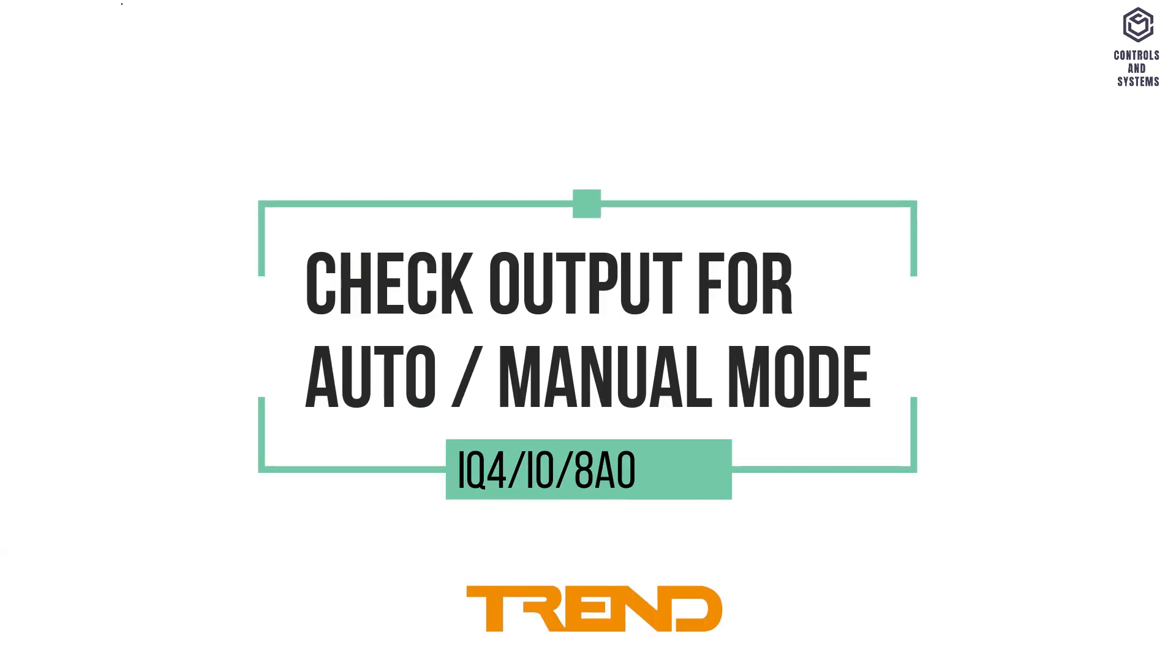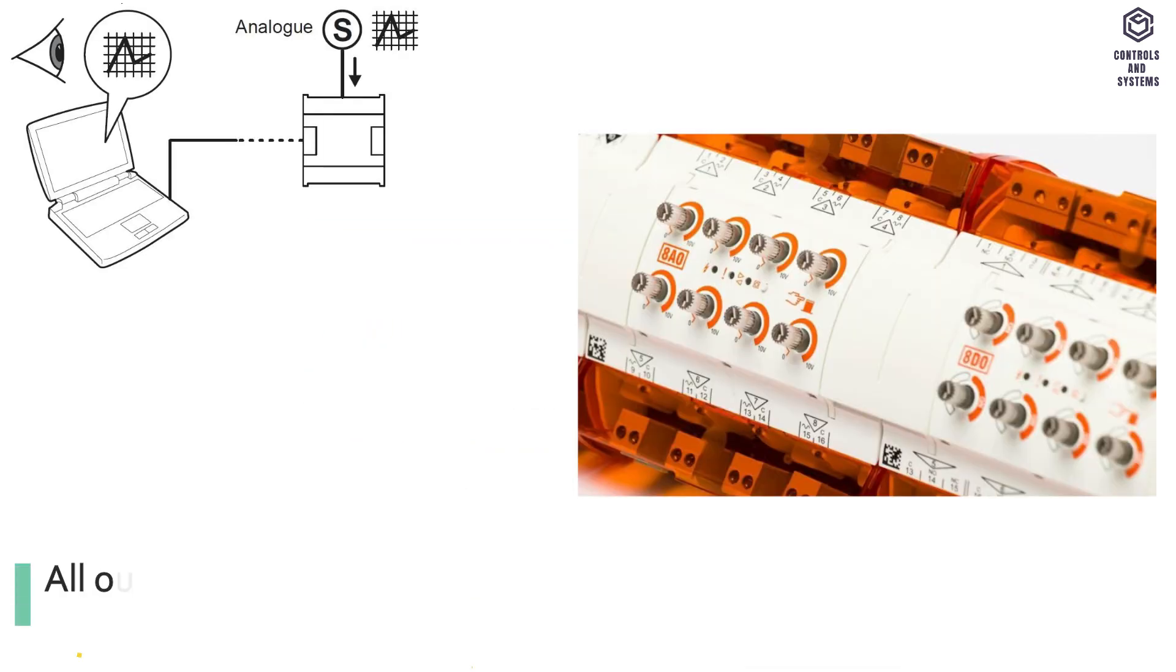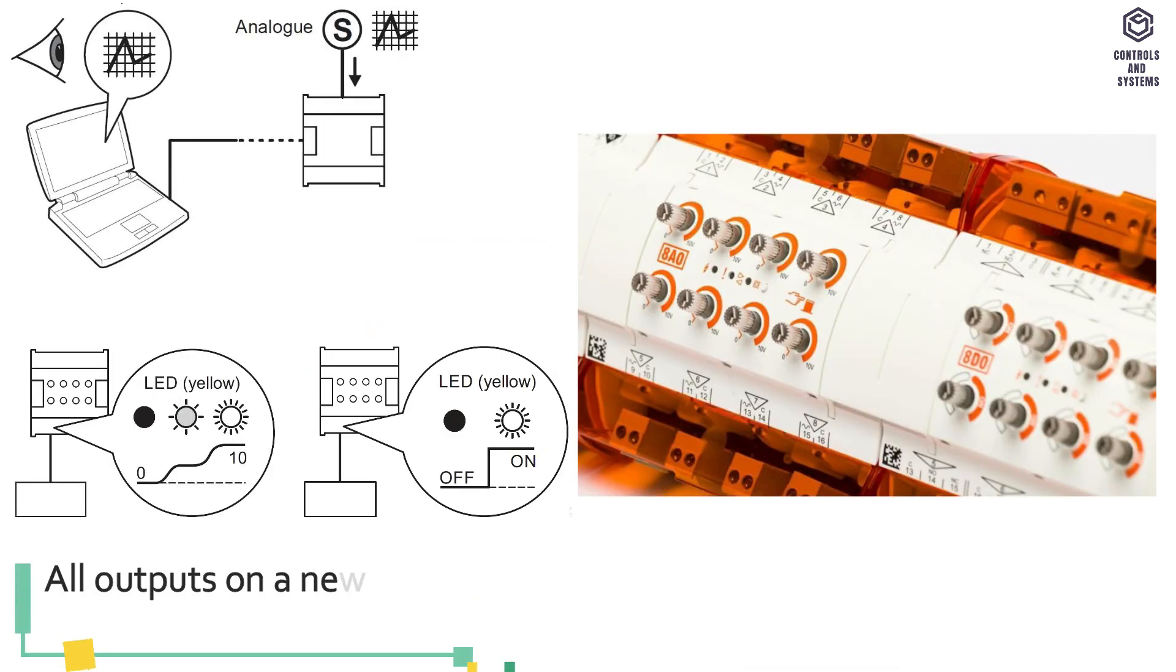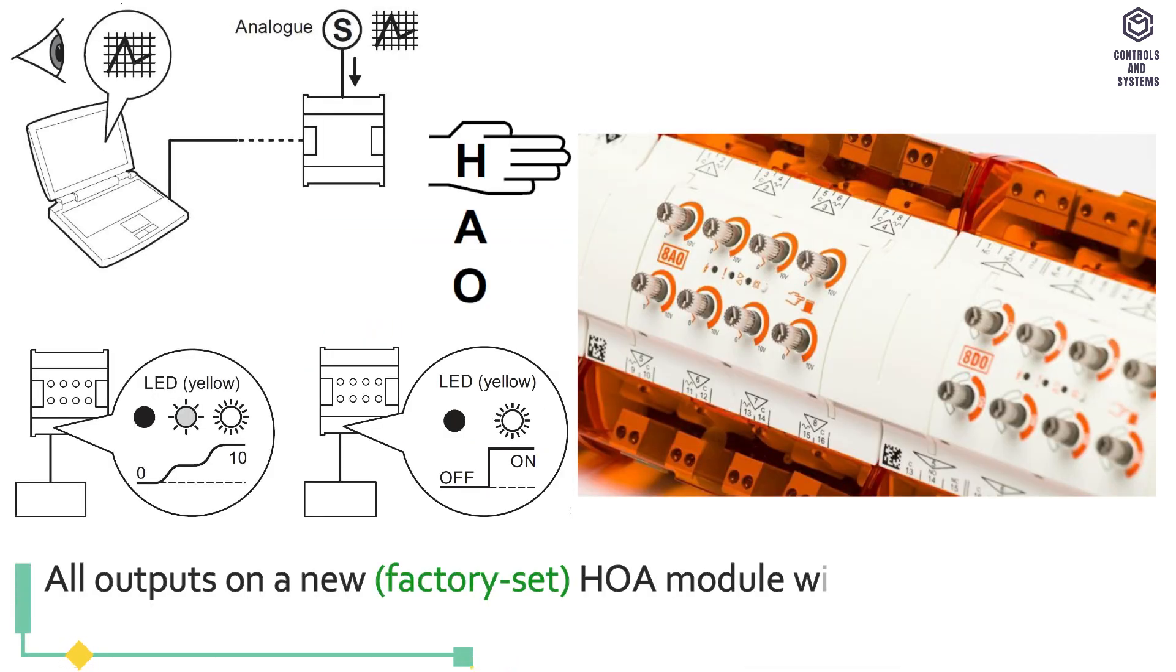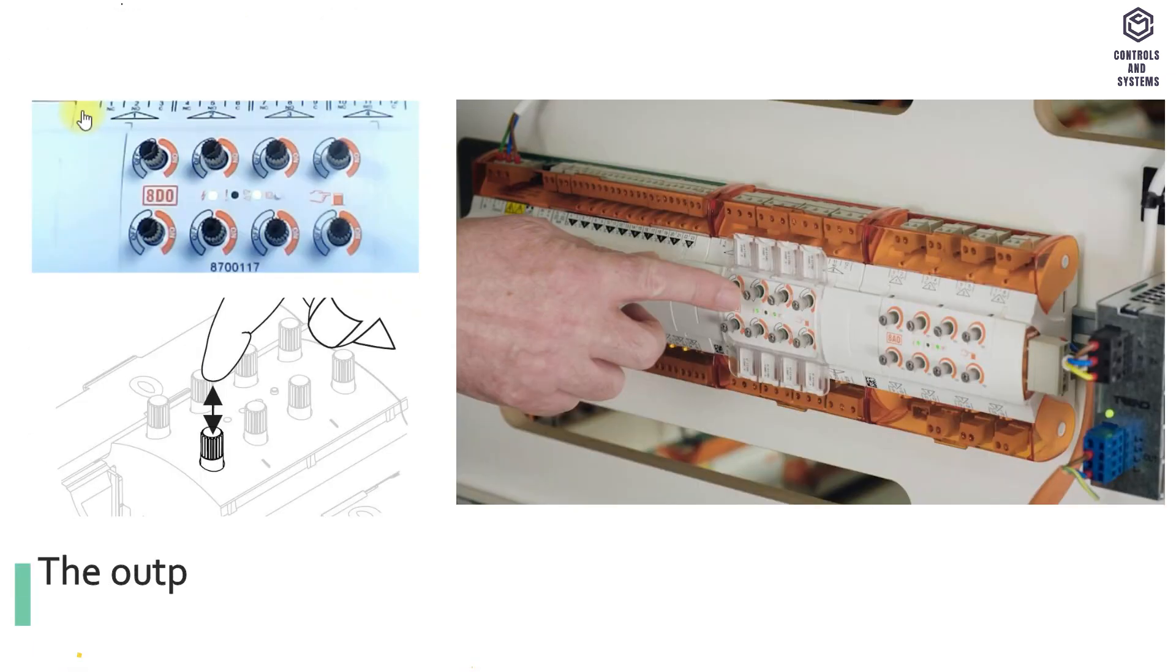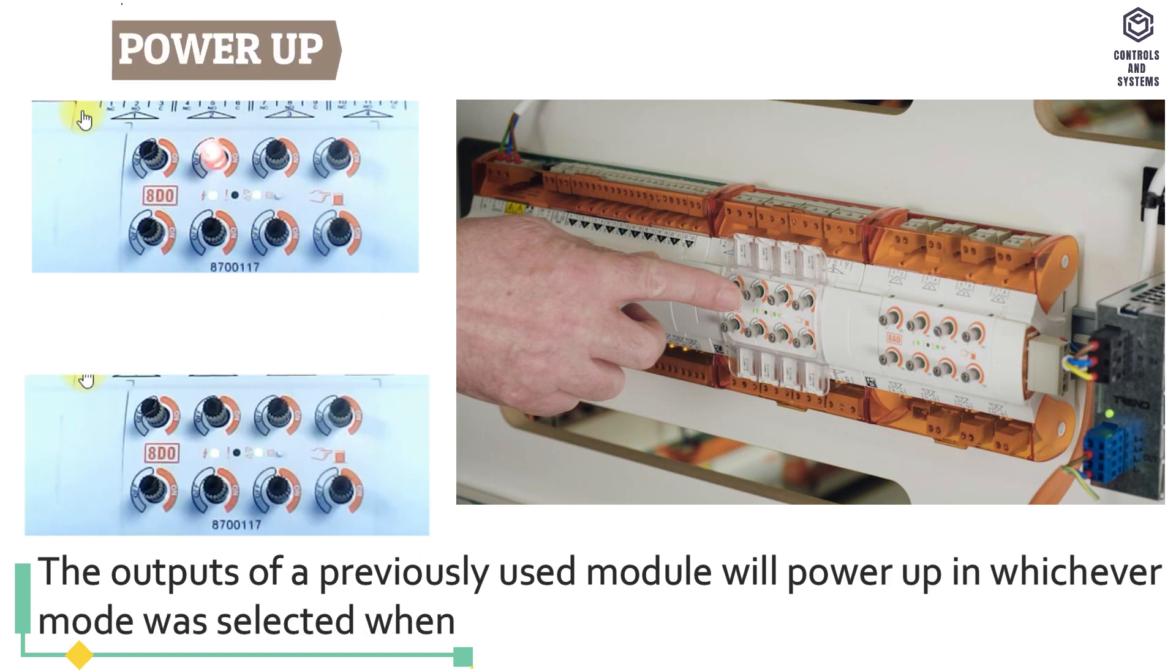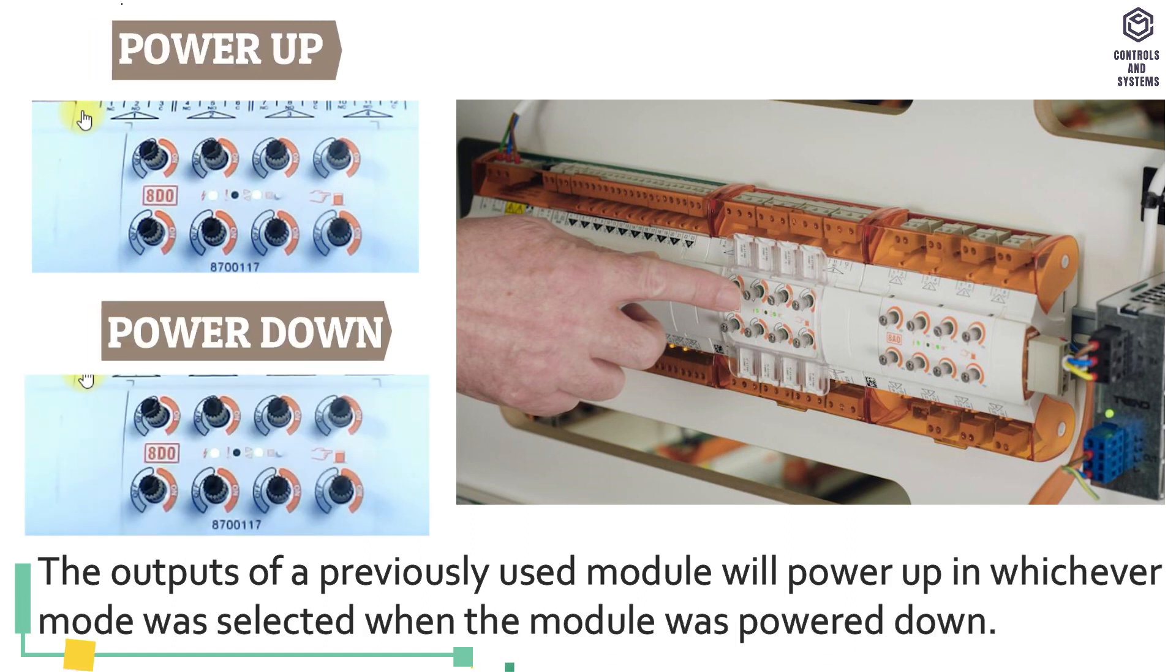Check output for auto manual mode. All outputs on a new factory set HOA module will power up in auto mode. The outputs of a previously used module will power up in whichever mode was selected when the module was powered down.